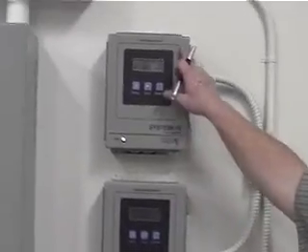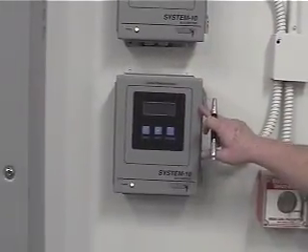Let's continue on. We do have these two meters right here. This is your hot water system. This is your chilled water system. These both feed into the BMS system, so you have the ability to track your tonnage, how much you're using, your BTUs per hour, your flow rates, all that kind of stuff. We use individual sensors. It gives a lot better accuracy to have individually calibrated sensors. So both of these do feed into the BMS system.